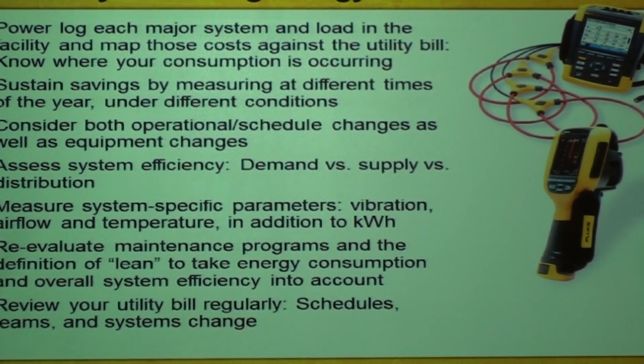Use a power logger or a power quality analyzer at the start to analyze your entire situation. See your energy consumption, check if there are excessive reactive powers, and compare it with your energy bill to make sure it tallies and there are no problems.